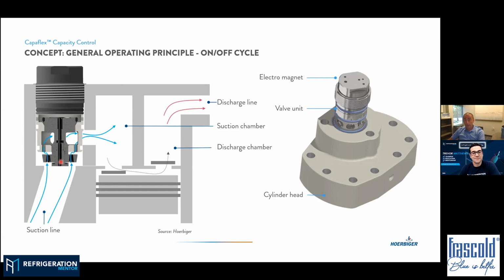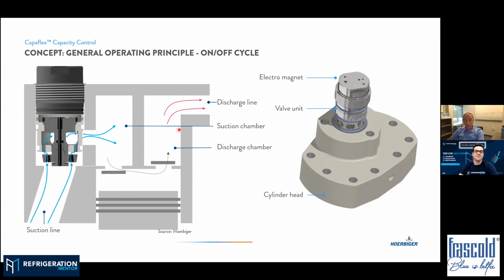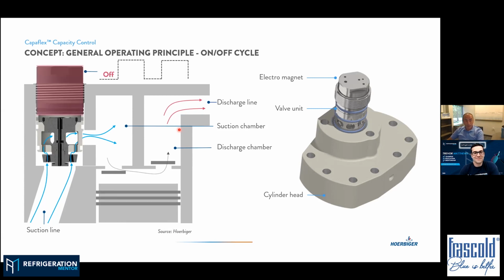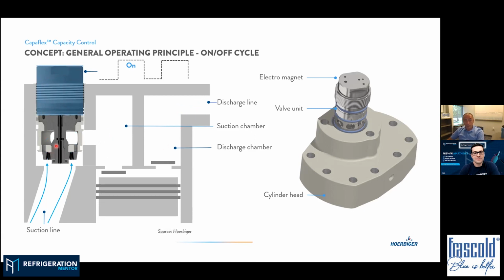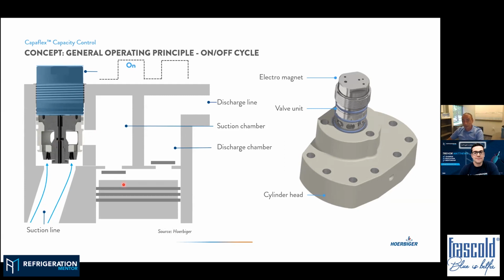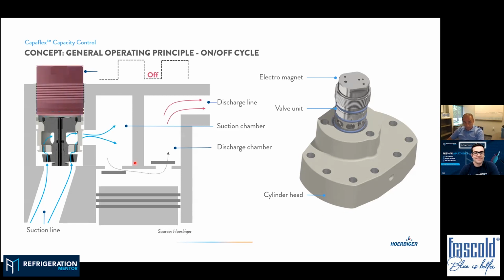So the gas is going through our capacity control valve. And as we see, the gas will flow through the suction reed and then to the discharge reed. So as a standard compressor, nothing different. This is not rocket science. But if the valve goes on, as we said, the valve will close the flow on the suction side. That means that the compressor has zero swept volume at this moment. And then, of course, if it is pulsed off, we will have the full load again on the head.